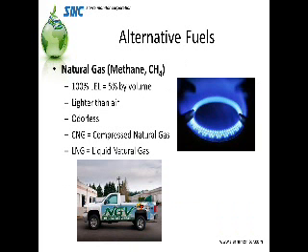The first fuel that we'll look at will be natural gas, chemical name CH4. Its explosive level is 5% by volume, meaning about 50,000 parts per million. That is 100% LEL. As a gas, it's lighter than normal air. It is odorless, and we see it in two forms. We see it both as compressed natural gas, from about 3,600 to 4,000 psi, and we see liquefied natural gas, which is cryogenic. They bring it down to minus 260 degrees Fahrenheit.